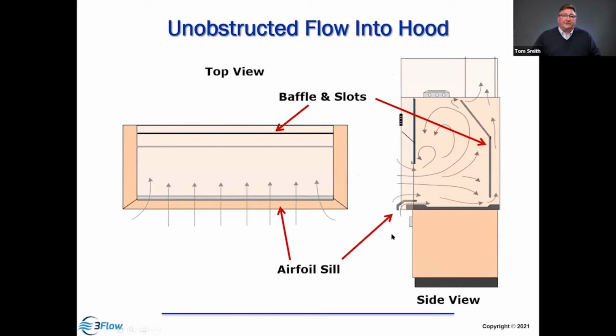When we look at a hood from the top view, the manufacturers build these hoods and they are somewhat like furniture. They're traditional size, stock sizes, but the airflow patterns are more complicated than just straight streamlines. If we look at it from the side, we get vortices that form in the top portion of the hood, and that has a rolling vortex, and then that airflow may split as it moves through the slots into the plenum and then out of the hood.